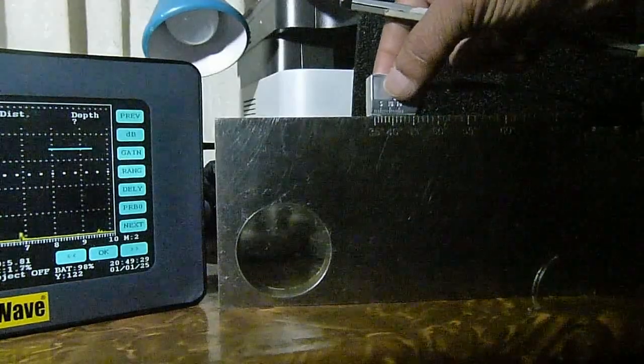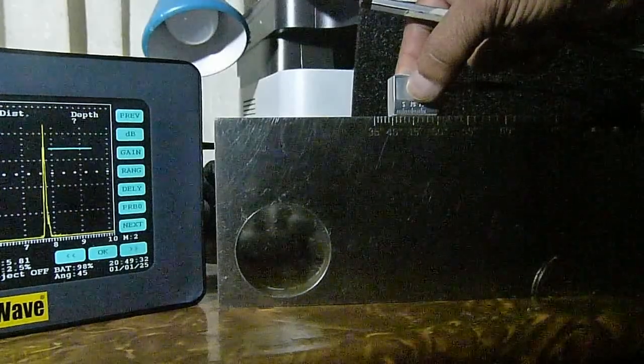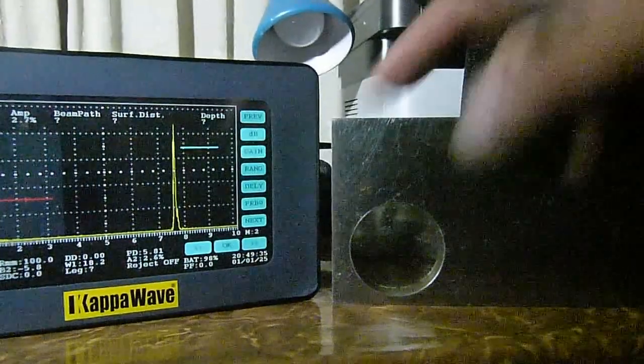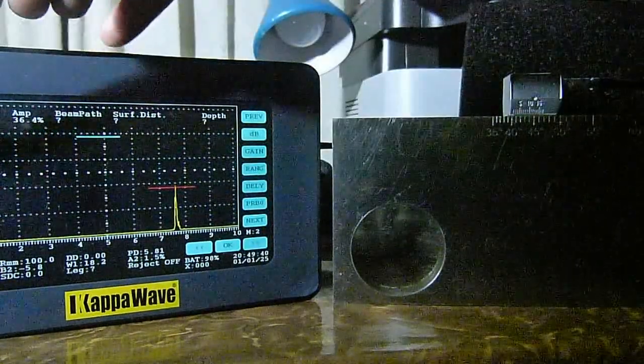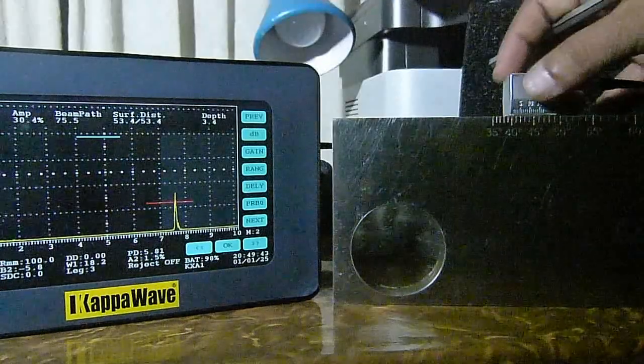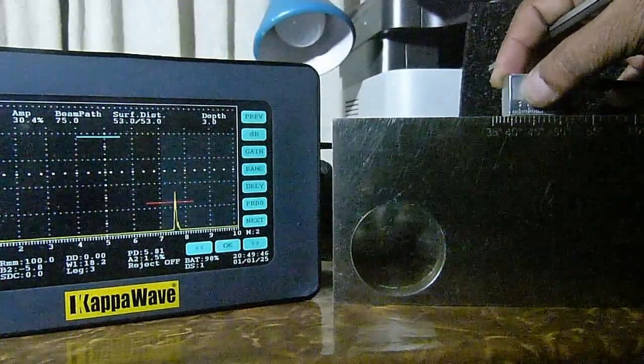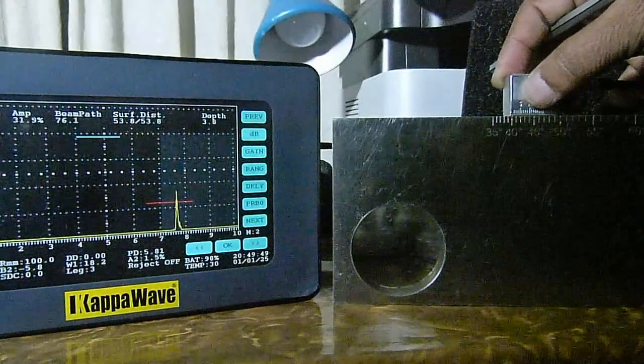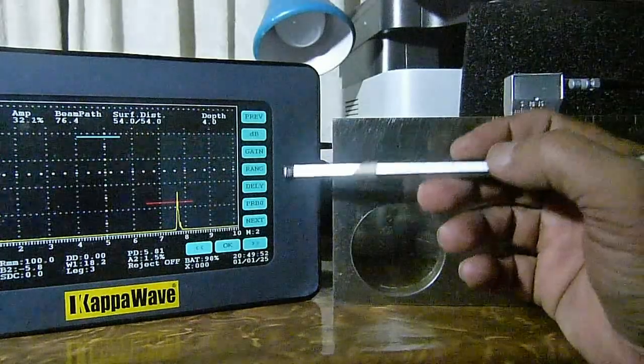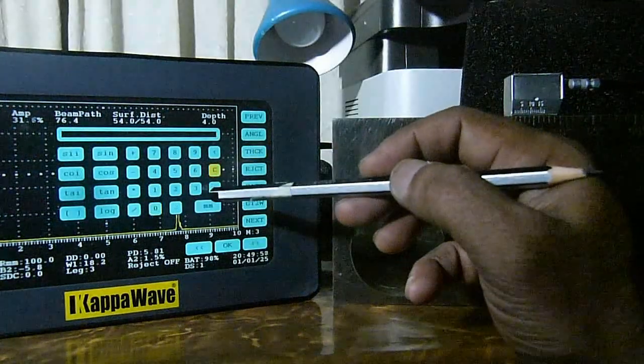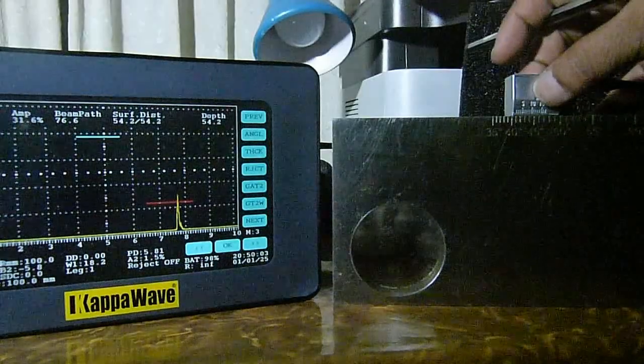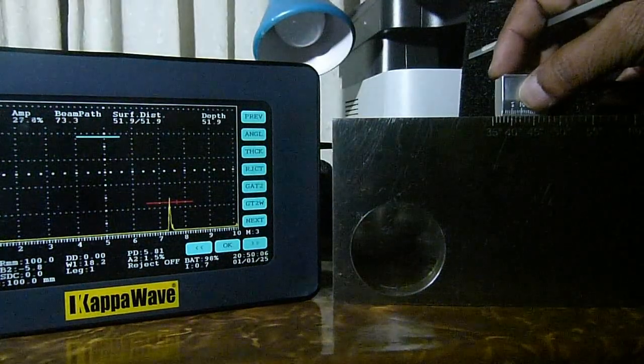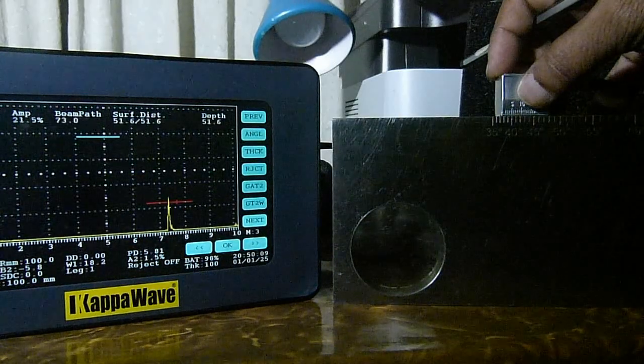Now the signal can be maximized. So once it is maximized, hold the probe in position, gauge the signal, and read your surface distance and beam path. Let us also insert the thickness of this material. That's 100 millimeter, being V1 block. So now it shows you the surface distance as 53 millimeter and the reduced surface distance as 40 millimeter.